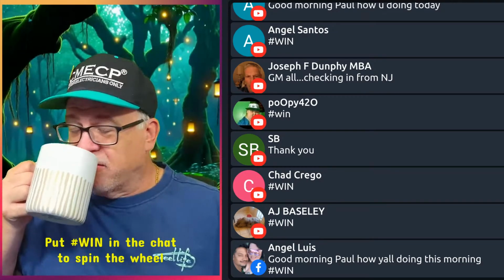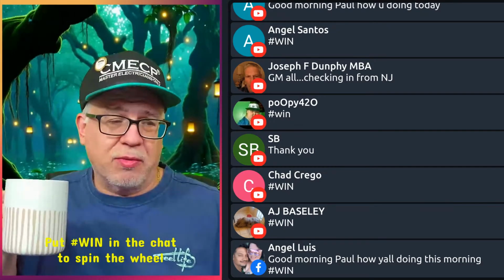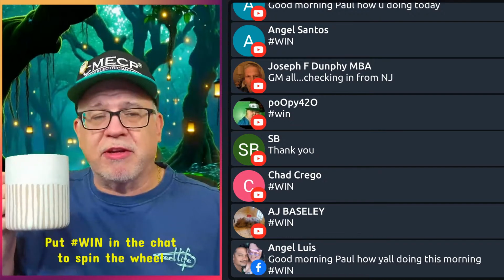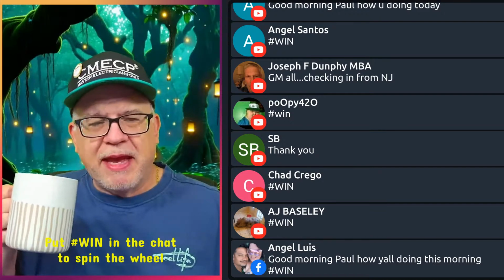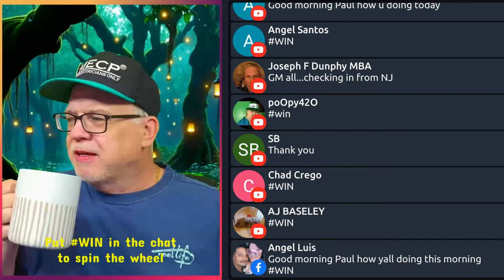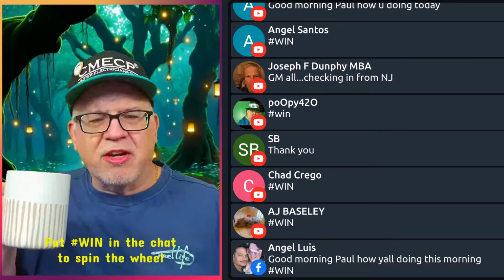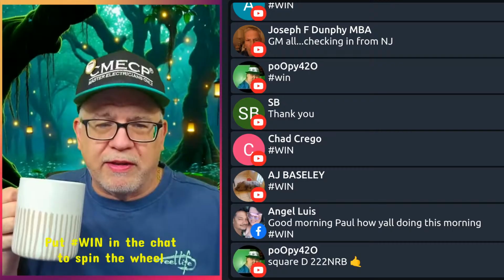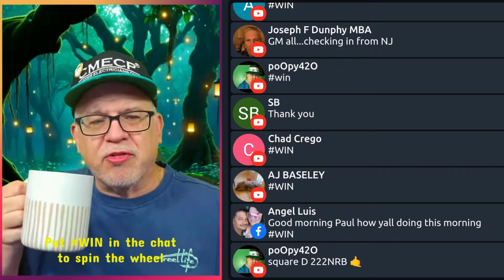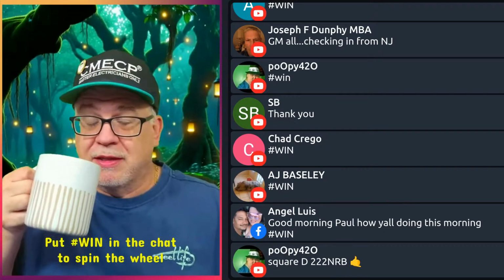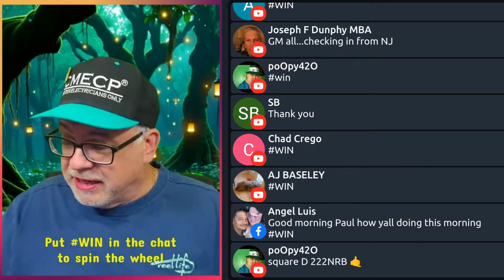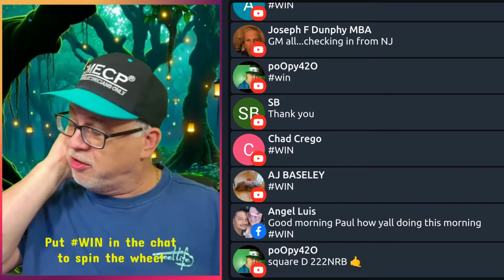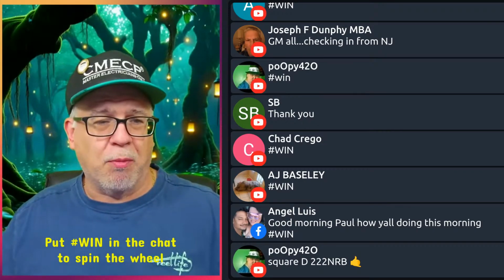Okay, so anyway, the guy did a video on TikTok or whatever it was. I can't remember. Angry shared it with me. And it just still amazes me, and he's so nonchalant about it, him being so right about it. And that's a personal choice, right? That's a personal choice, but he's wrong. It is not required for MC cable to use an anti-short bushing. If you want to use it, knock yourself out, bro.